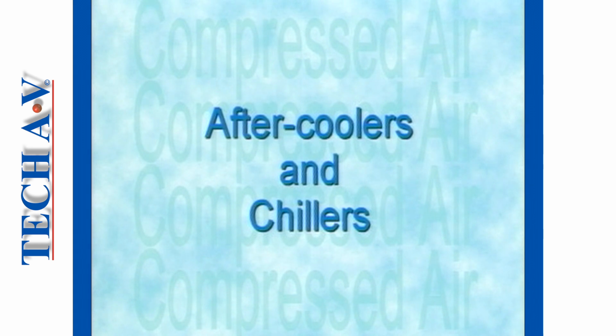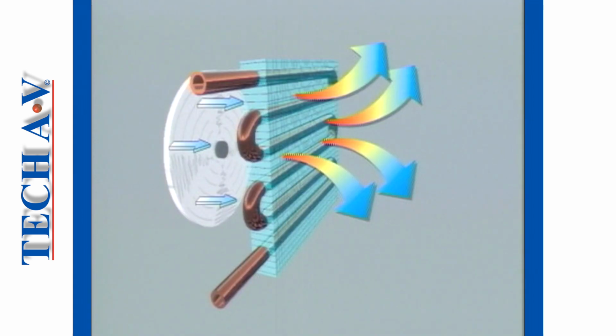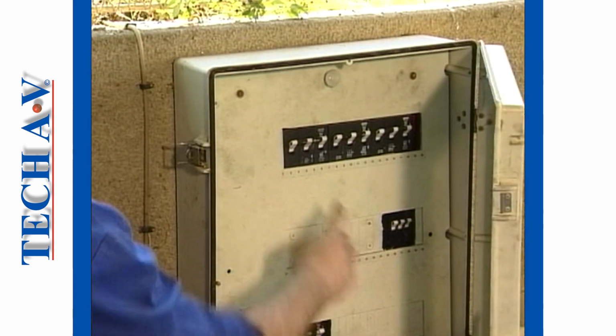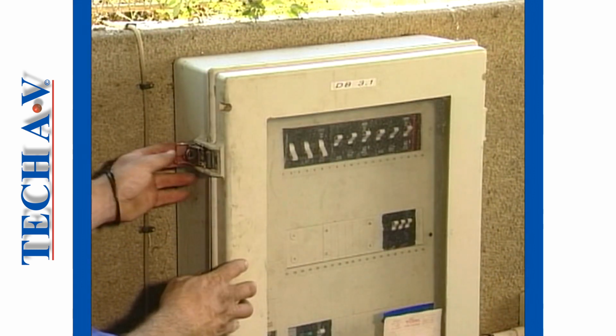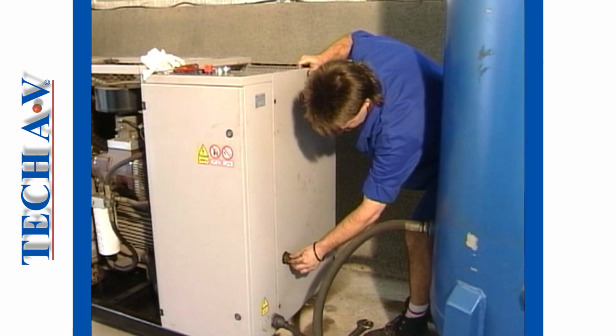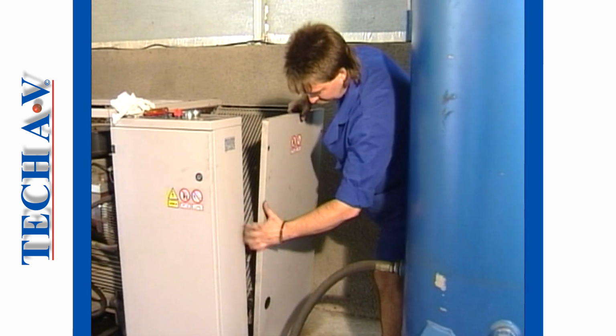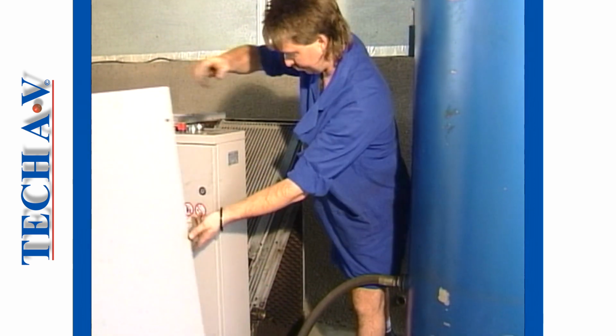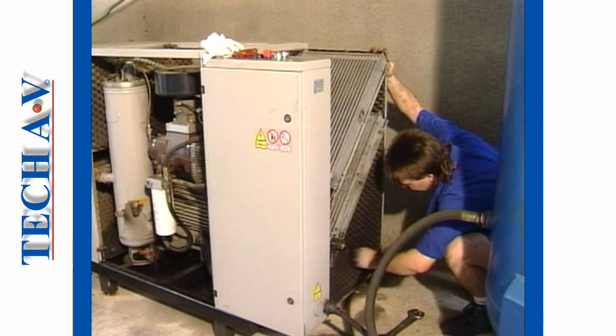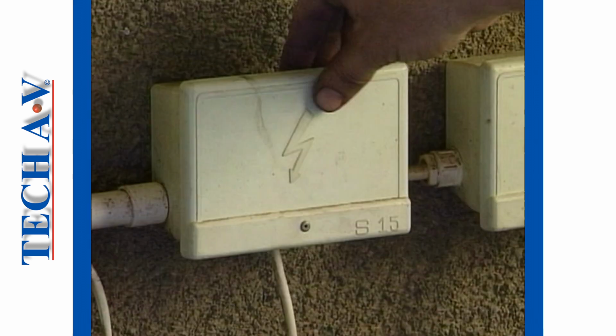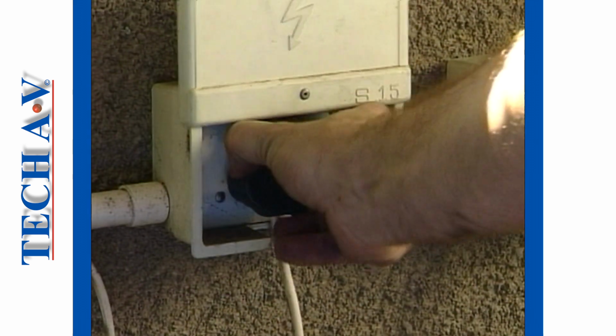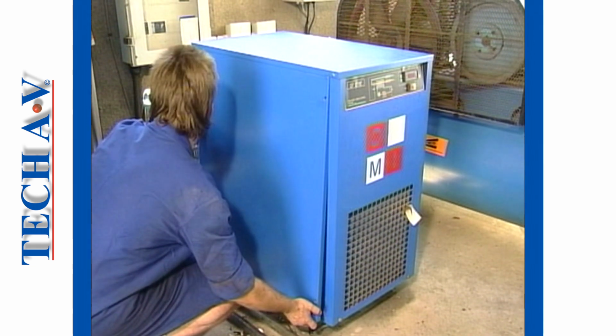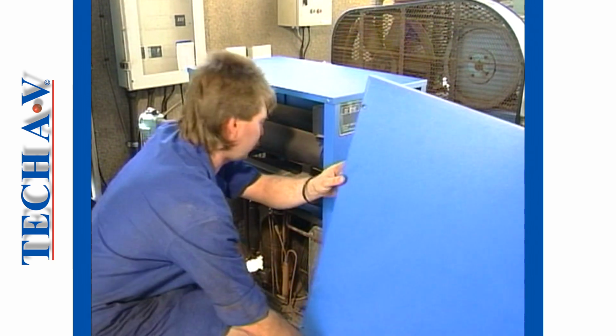We next deal with the basic maintenance involved with aftercoolers and chiller units. It must be remembered that coolers will be in the vicinity of a fan. For this reason, it is important that the power supply to the unit is isolated. Remove the necessary covers or guards in order to gain access to the aftercoolers on rotary screw compressors. In the case of refrigerated chillers, first make sure that the independent power supply has been isolated. Again, it will be necessary to remove the side covers to gain access to the unit.